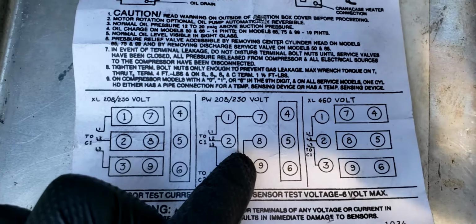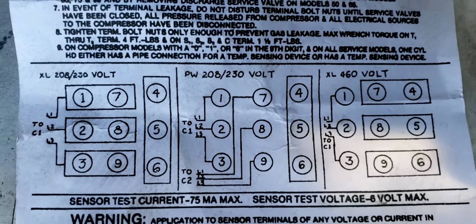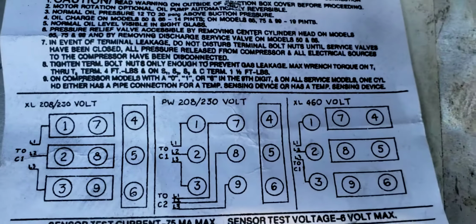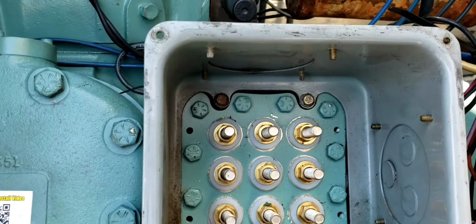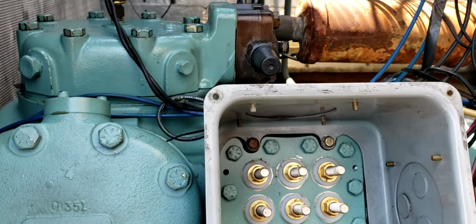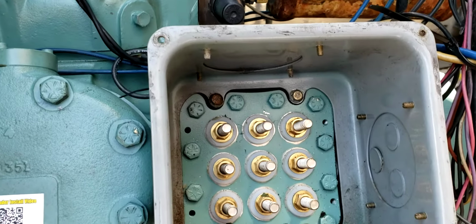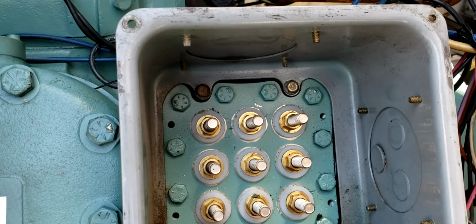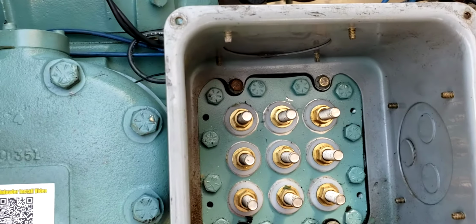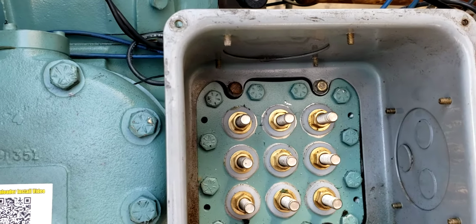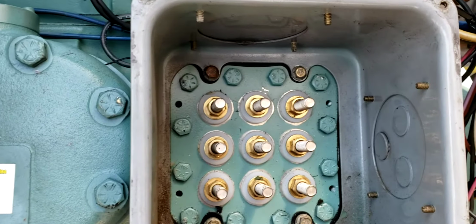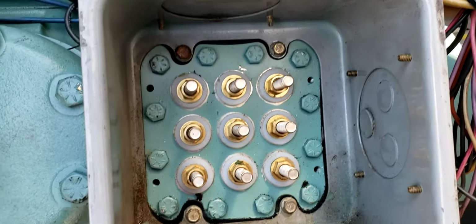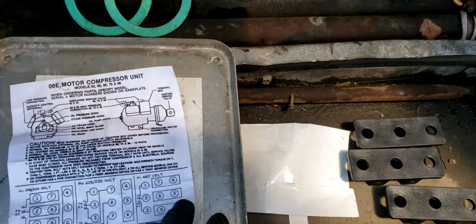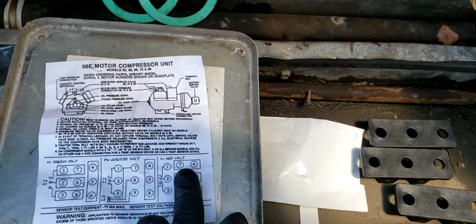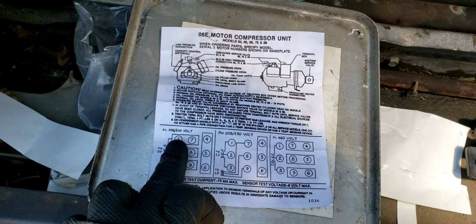So let's move on to if you're using the part winding. Now, this compressor, because of its size and the inrush current or the locked rotor current, you have the ability to do this part winding start. If you're a pro, you may or may not know what it is. If you're a beginner, more than likely you won't know what is meant by across the line or part winding start. But this right here option is across the line.